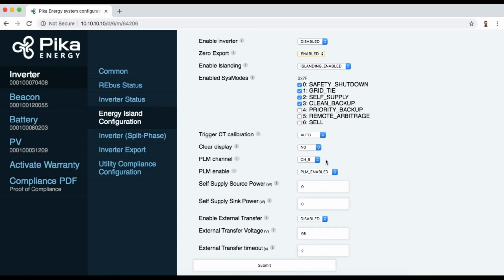In that case, you would connect to the first inverter, and you would connect the beacon and change all those PLM channels to the PLM channel of the first inverter that you power on and all of its subsequent devices to channel 2. And then you would go to the second inverter and program that inverter and all of its subsequent devices on its own PLM channel. In the event that you were doing whole house backup, you would enable external transfer. In this case, we do not have an external transfer switch. We are just backing up a 50 amp protected loads panel, so we're going to leave this disabled.